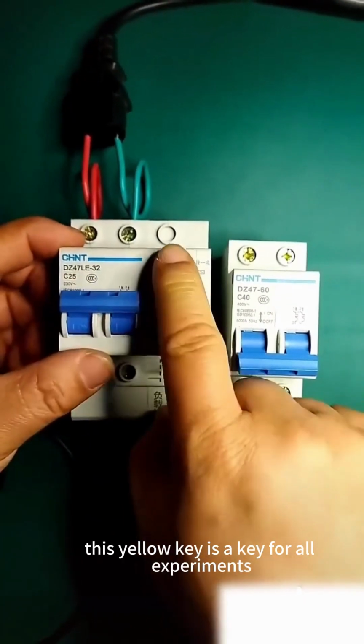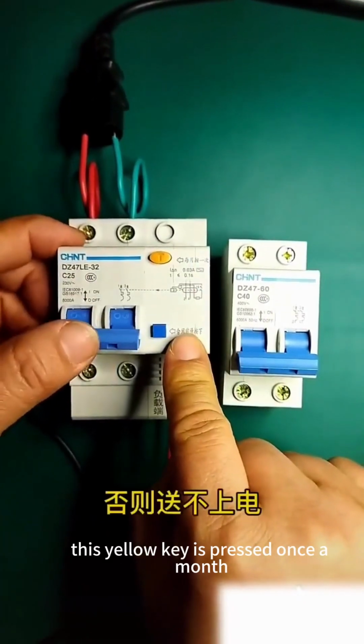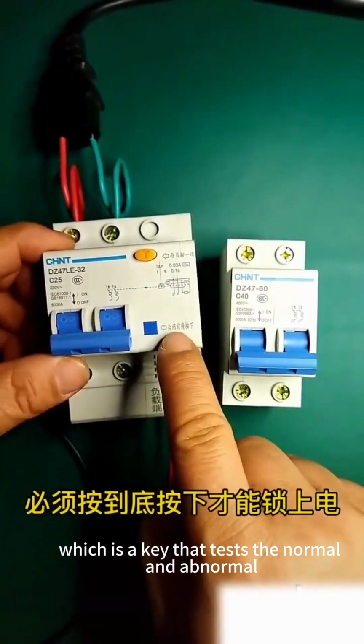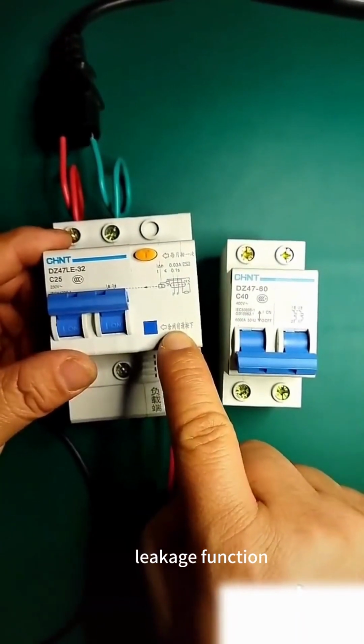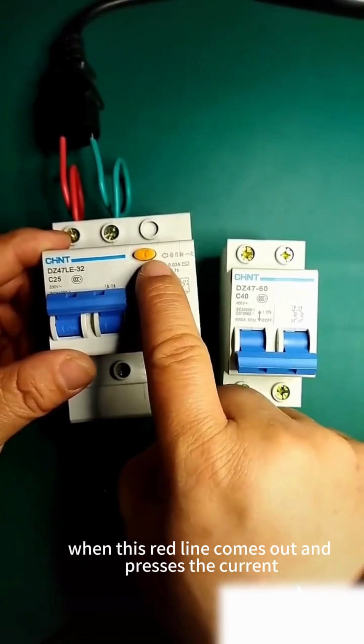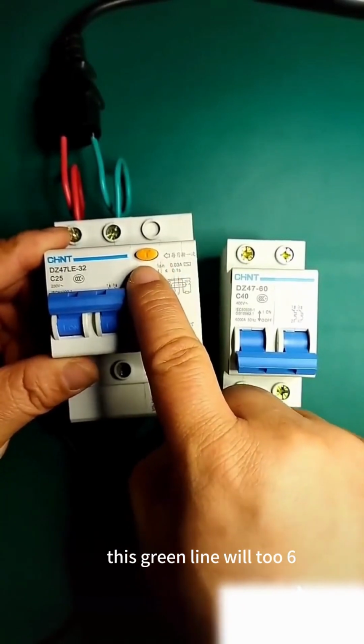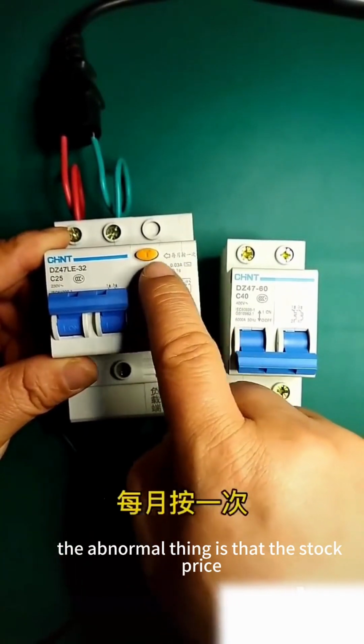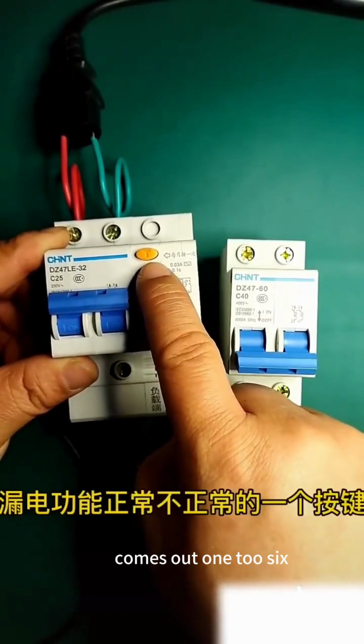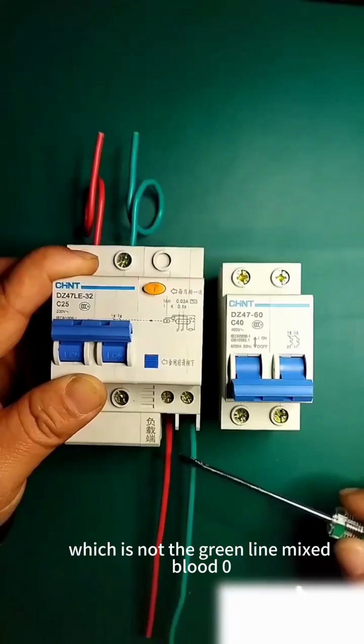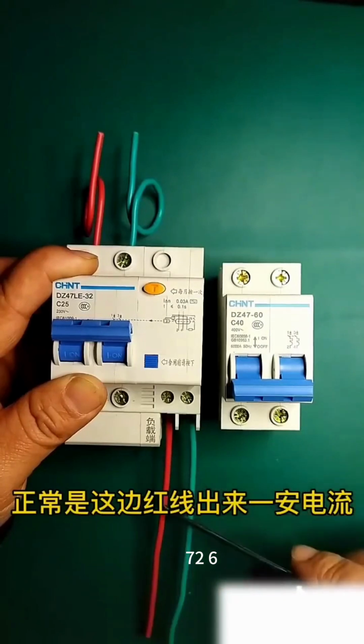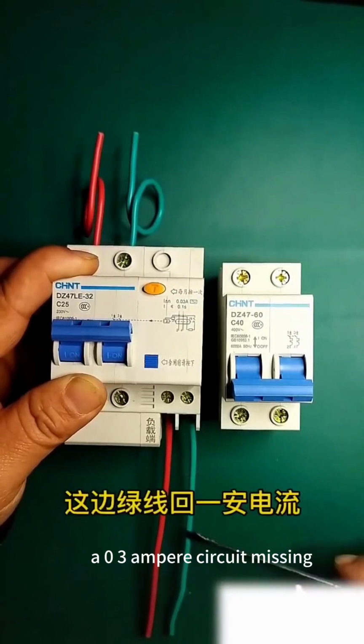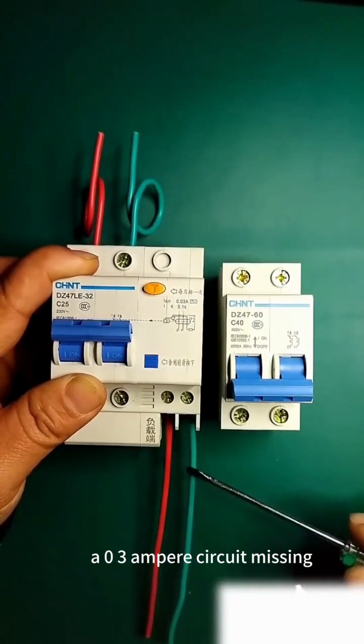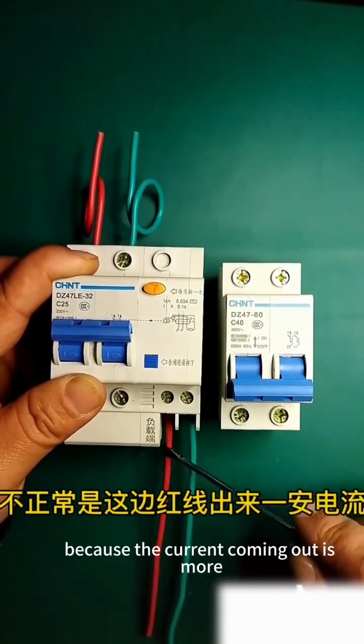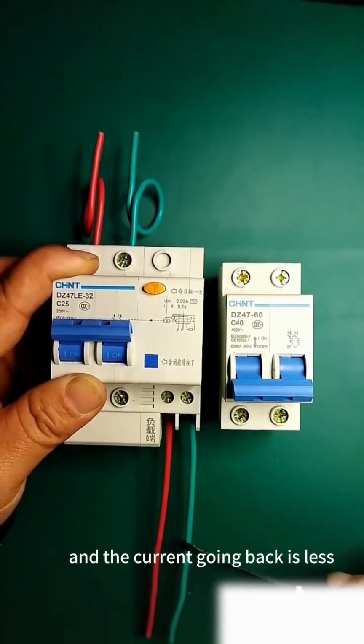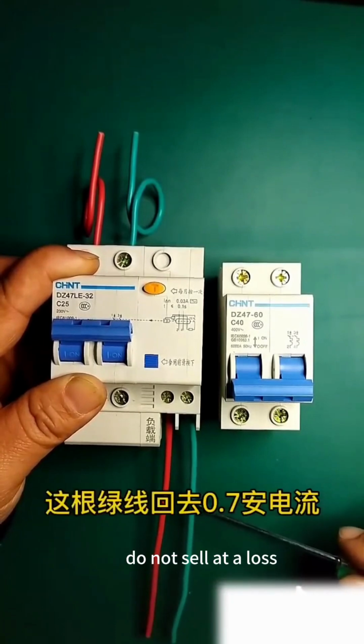This yellow key is the test key. This yellow key is pressed once a month, to test the normal and abnormal leakage function. Normally, the current going out through the red line comes back through the green line. In the abnormal case, the current going out is more and the current coming back is less, so it trips at a leakage of 0.03 amperes.